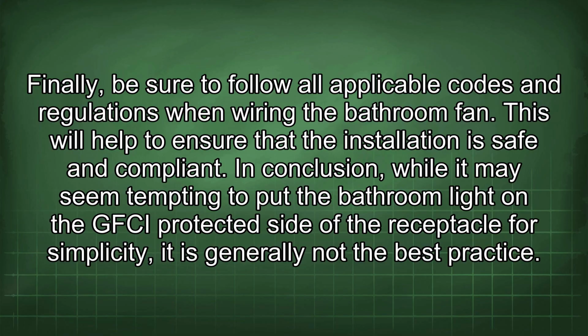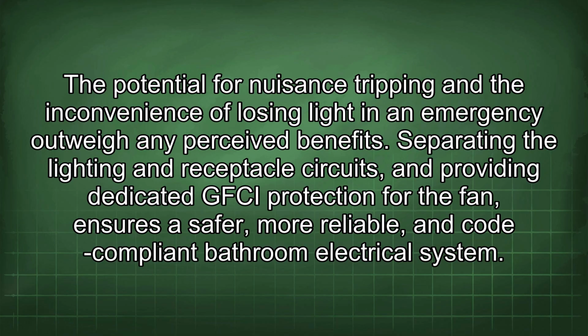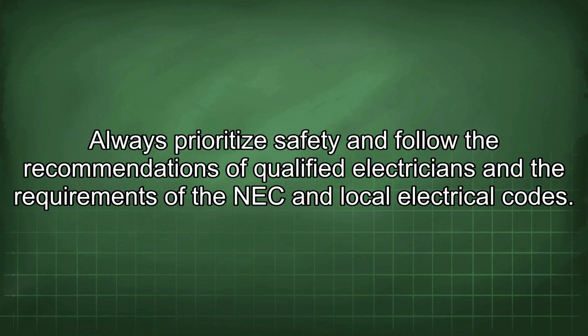In conclusion, while it may seem tempting to put the bathroom light on the GFCI protected side of the receptacle for simplicity, it is generally not the best practice. The potential for nuisance tripping and the inconvenience of losing light in an emergency outweigh any perceived benefits. Separating the lighting and receptacle circuits and providing dedicated GFCI protection for the fan ensures a safer, more reliable, and code-compliant bathroom electrical system. Always prioritize safety and follow the recommendations of qualified electricians and the requirements of the NEC and local electrical codes.